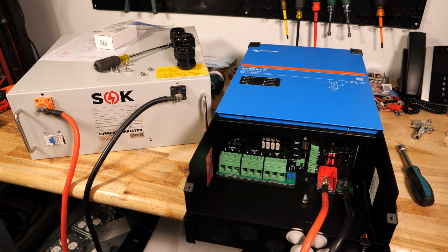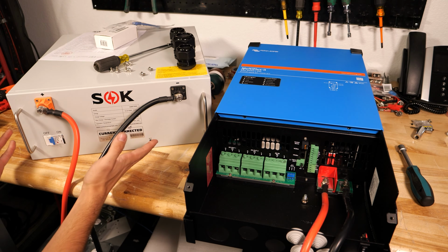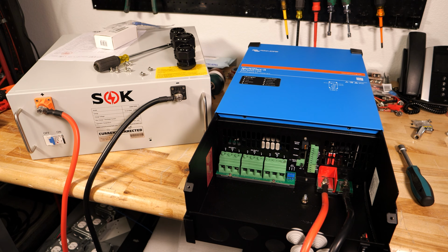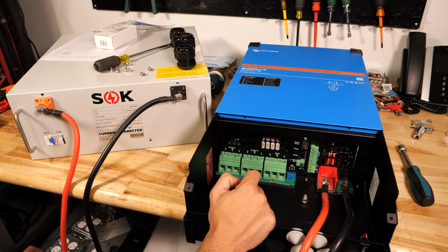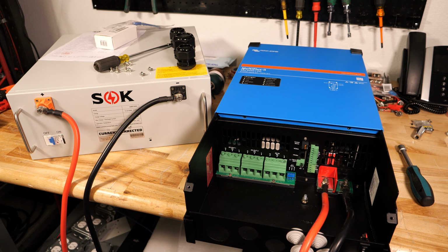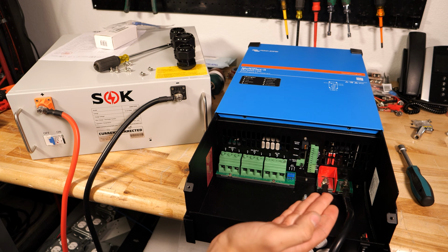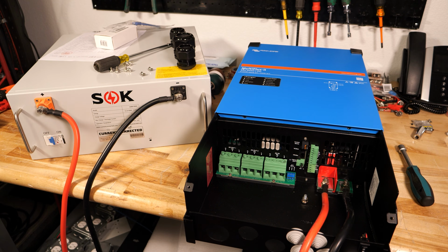Now, what better way to test the new Victron inverter than with the new SOK 48V rack mount battery? I've got this hooked up with a set of my 4-gauge Anderson cables. Ideally, this inverter, if you were using normal battery cable, you would be using 1/0 cable. However, for my case, I'm just here on the test bench, running a whopping 4 feet between the two, so I should be fine.